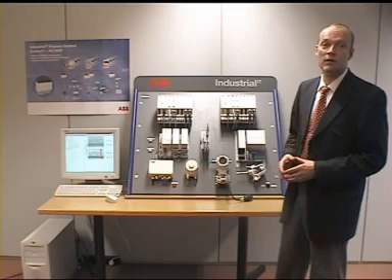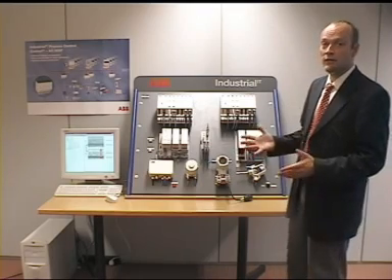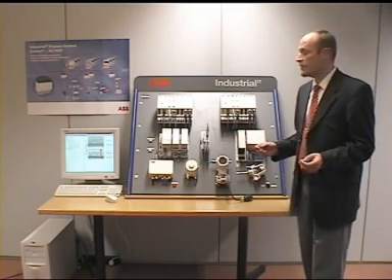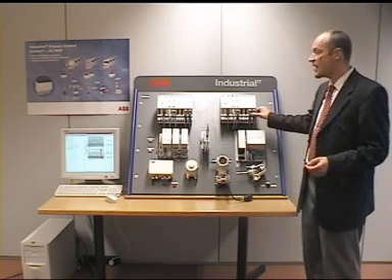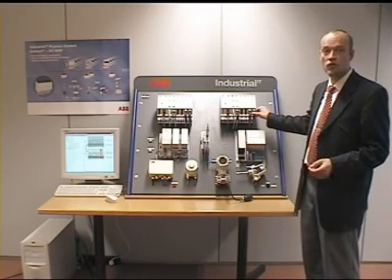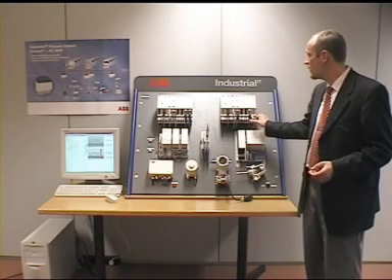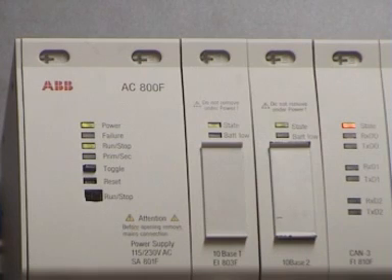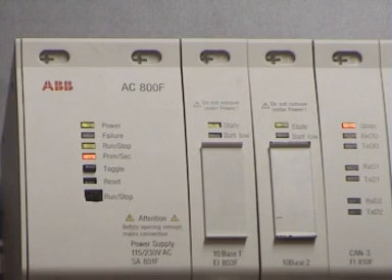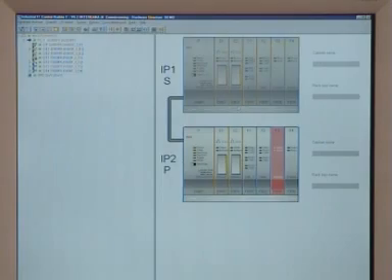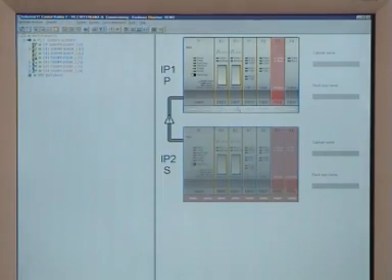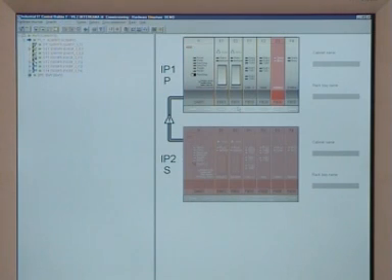Let's make an example. I would disconnect the PROFIBUS line from the active controller and we see it directly switches over to the second controller without any interruption in the PROFIBUS line, that means no interruption to the process.